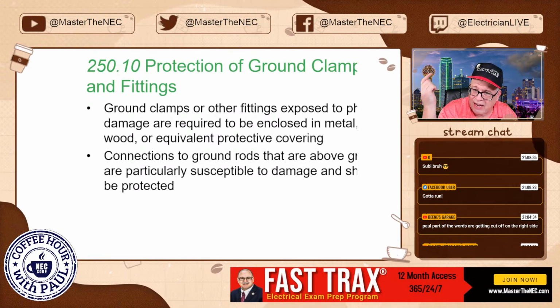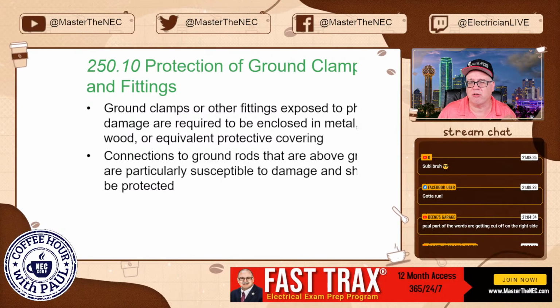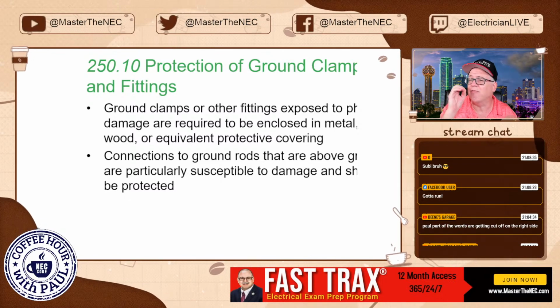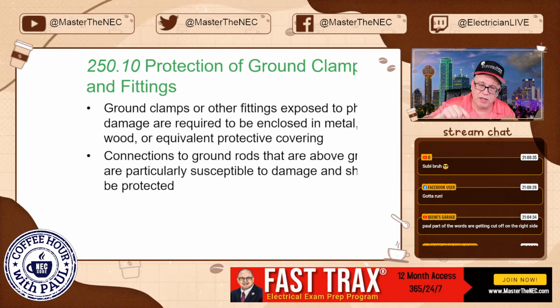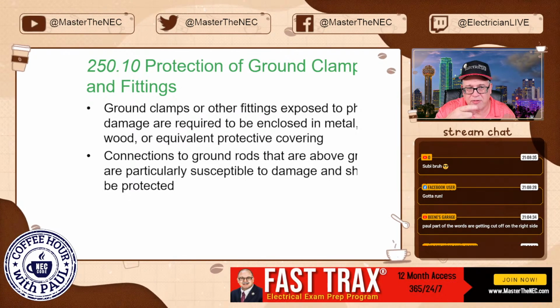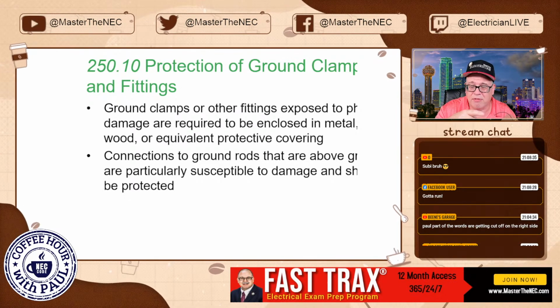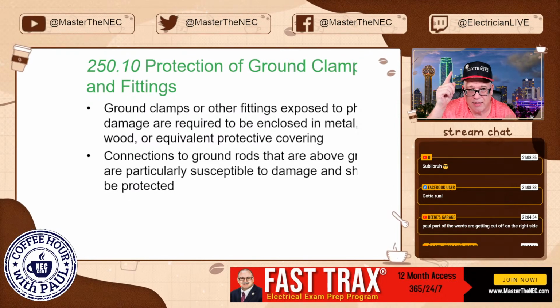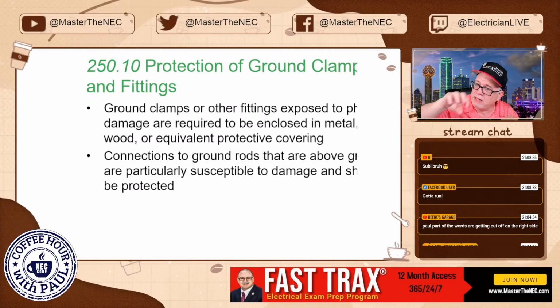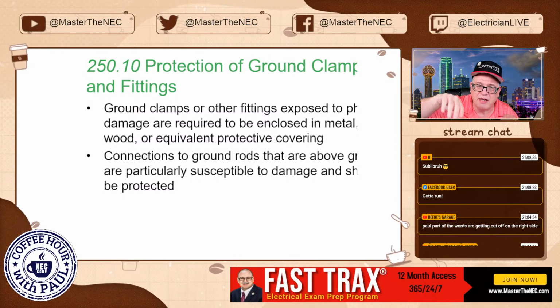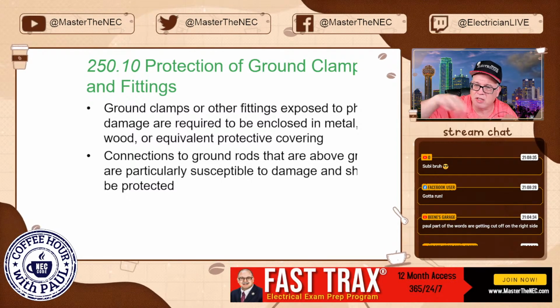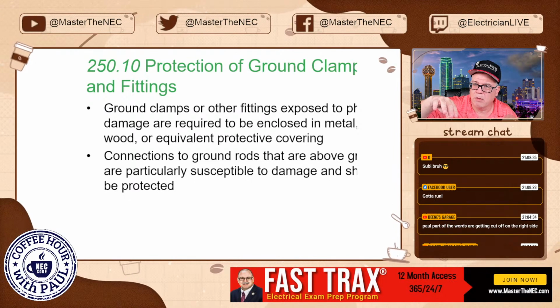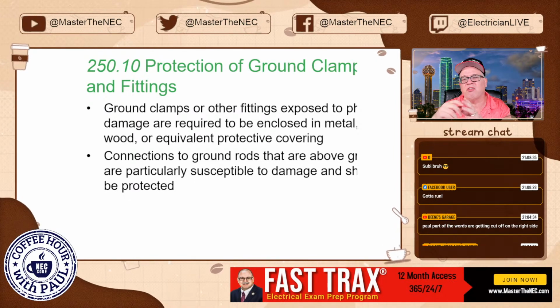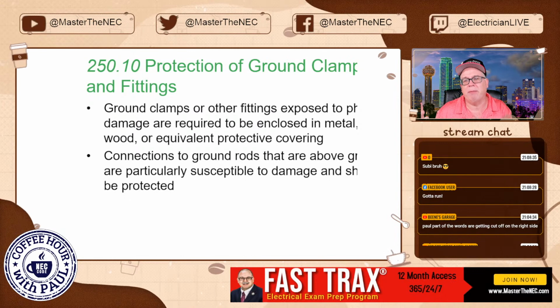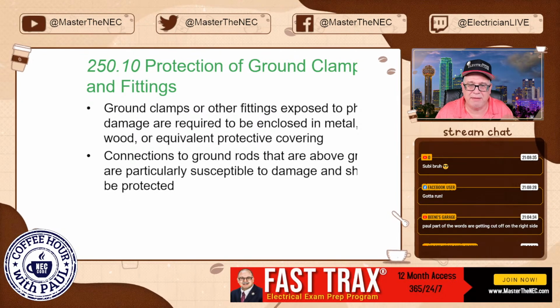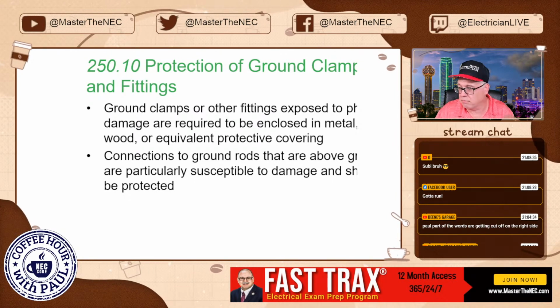When I first moved into the house I'm in now, I went right out to the ground rod, because I'm a nerd like that. I went right out to the ground rod, and it was a little above grade. Nobody in the comments say, did you redrive it? I'm not going to answer that. I plead the fifth. And what it was, it was just spinning around because the lawnmower kept hitting it and it knocked it loose, right? So it was subject to physical damage, being knocked loose, so it has to be protected. Easiest way to achieve that is to drive it below grade. Don't have to worry about it.